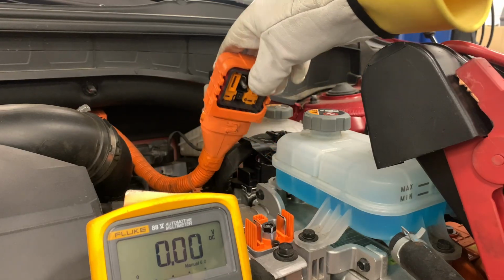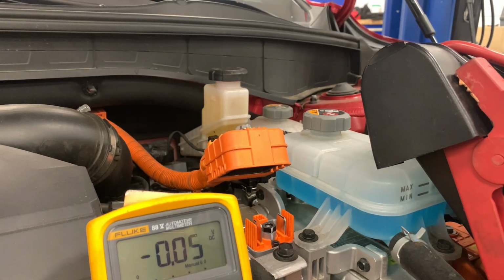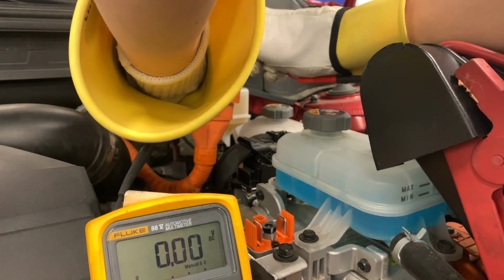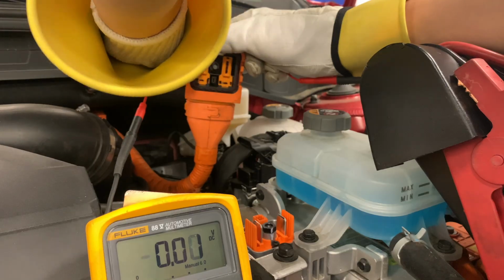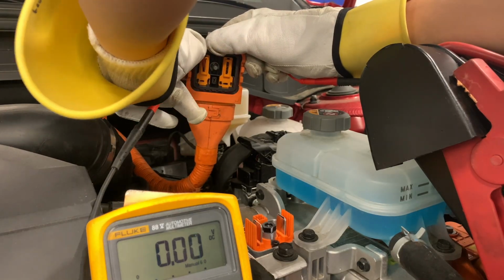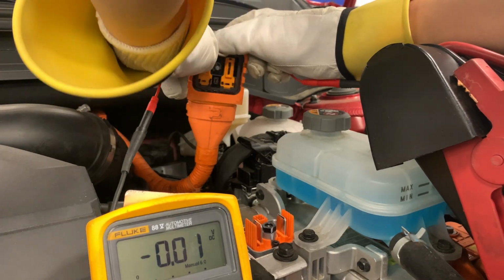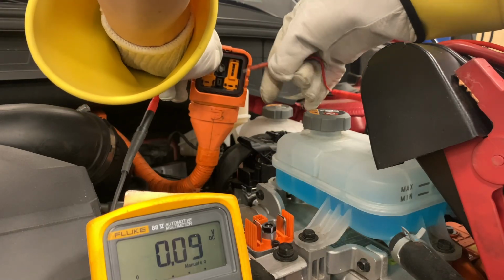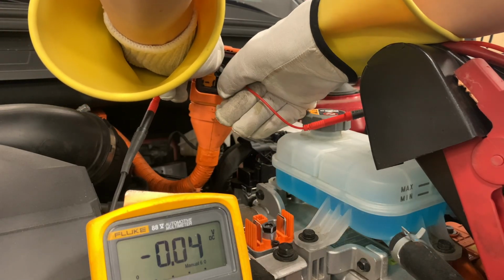Now we want to check the cable coming from the high voltage battery. Here's the cable. I'm going to do my best to make good contact inside there with these terminal test leads — I picked these for the purpose of being able to make good contact.